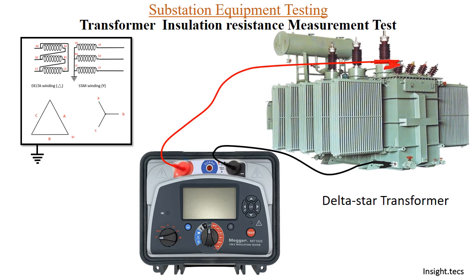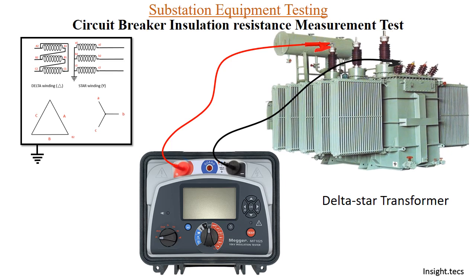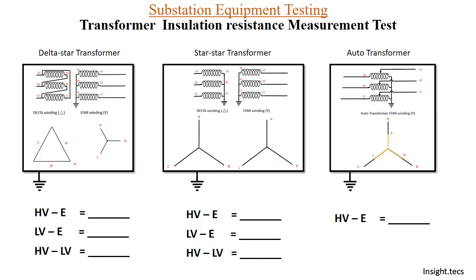For LV to earth at ten minutes, the reading is 4.20 giga ohms. The third reading is for HV to LV, so we change connections accordingly from HV to LV, set to 5 kV, and take the measurement. For one minute we get 3.63 giga ohms, and for ten minutes we get 7.18 giga ohms. For the delta-star transformer we take three readings: HV to earth, LV to earth, and HV to LV. Similarly for star-star, three readings; for auto transformer, only one reading — HV to earth.